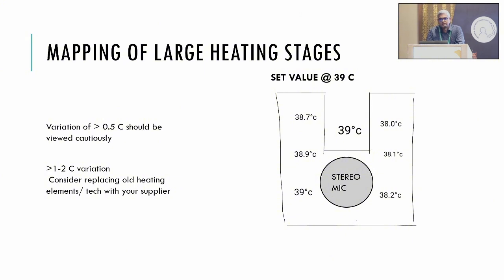Many of us have a practice, because of the air gap under the dish, of commonly increasing the temperature of the laminar flow to 38 or 39. Some people even keep it at 40. So it's very important to identify these spikes. If there is more than a 2 degree variation, then you should consider replacing the heating element or discuss it with your supplier.